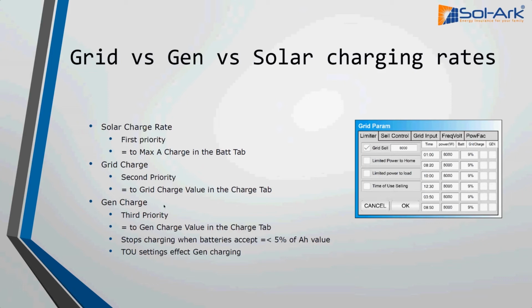And a quick note on the generator charging setup is that if we call for a generator to charge the battery back up, we will continue to charge the battery using the generator until the battery accepts equal to or less than 5% of the amp hours for the battery bank. I know it's a bit of a mouthful, but basically, if you had a 100 amp hour battery, we would keep charging that battery from the generator until the battery accepted 5 amps or less. That's how we determine when it's close enough to full that we should turn the generator off.